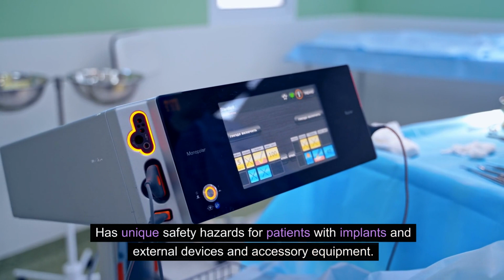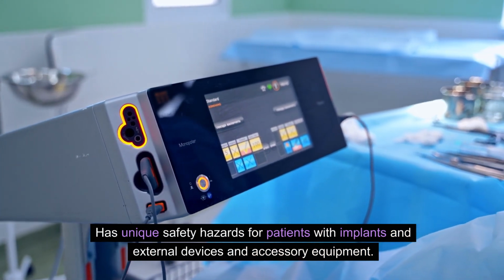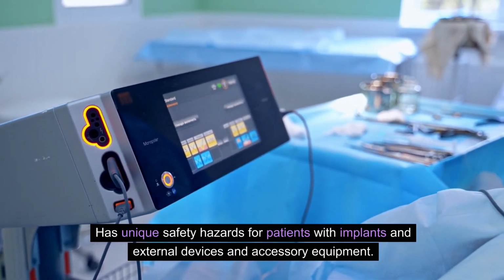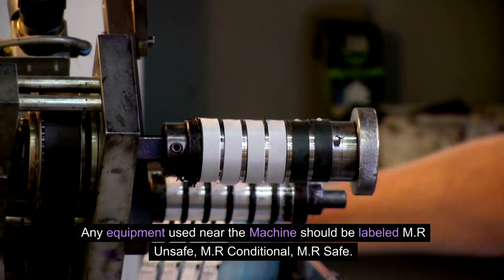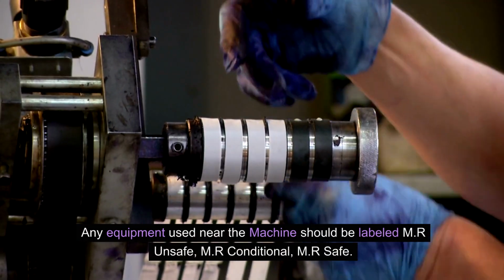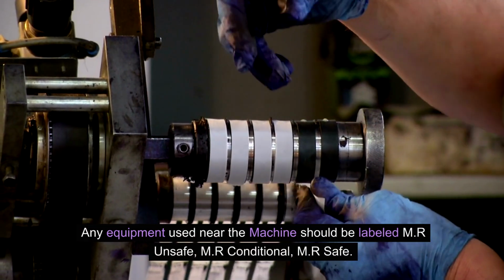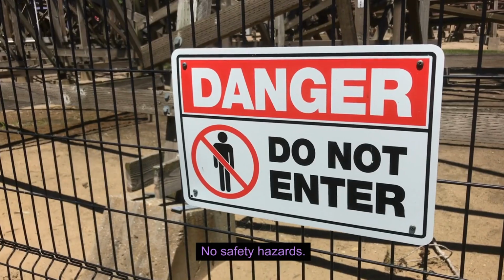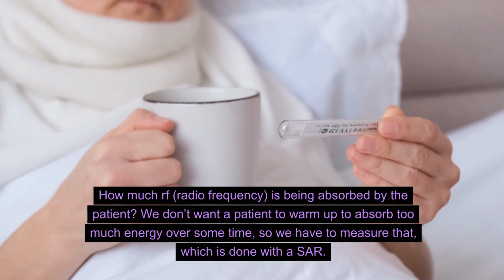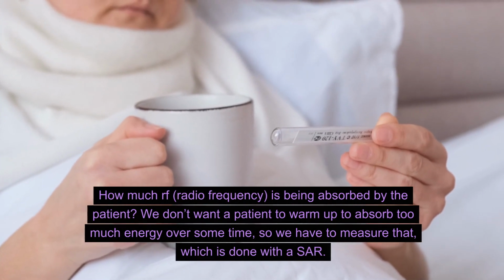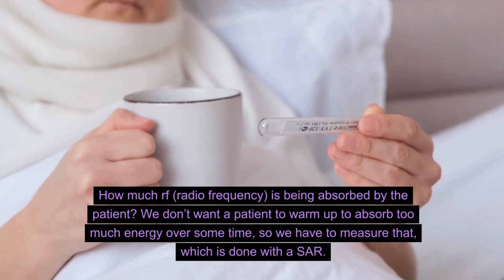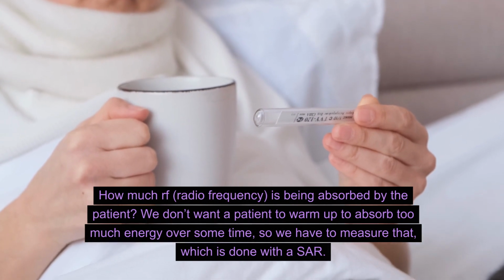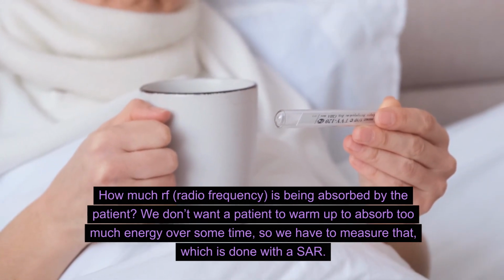MRI has unique safety hazards for patients with implants and external devices and accessory equipment. Any equipment used near the machine should be labeled MR unsafe, MR conditional, or MR safe. Specific absorption rate (SAR): how much RF, radio frequency, is being absorbed by the patient? We don't want a patient to warm up by absorbing too much energy over some time, so we have to measure that, which is done with the SAR.